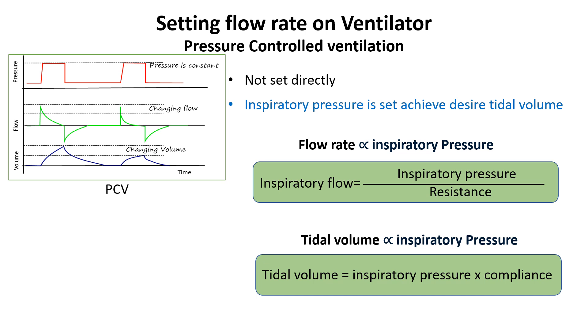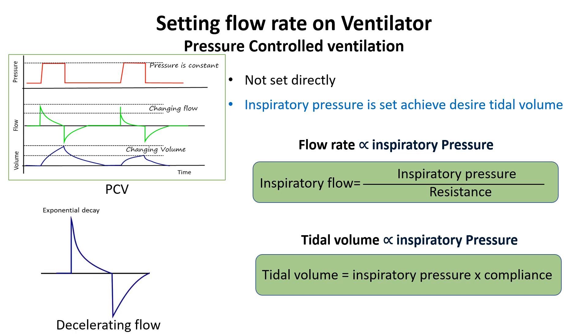The flow pattern in pressure-controlled ventilation is decelerating. Flow is driven by the pressure gradient between the ventilator and the lungs. At the start of inspiration, when the pressure difference is greatest, flow is at its peak. As the lungs fill and alveolar pressure rises, the pressure gradient decreases, leading to a progressive decline in inspiratory flow.